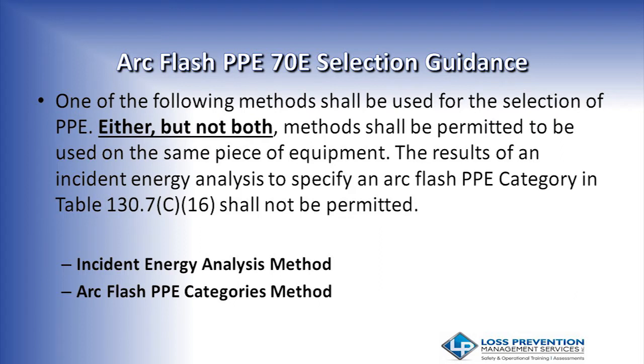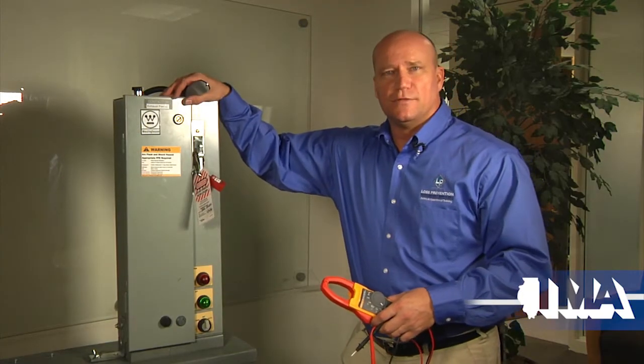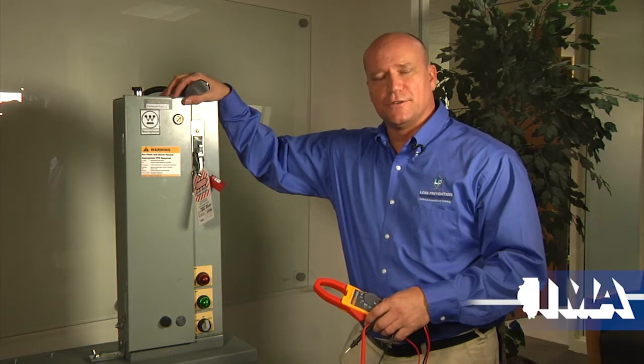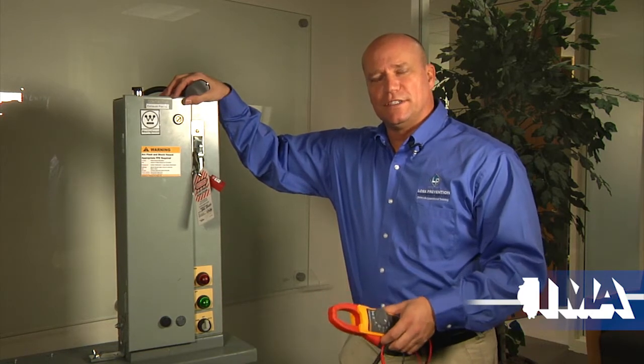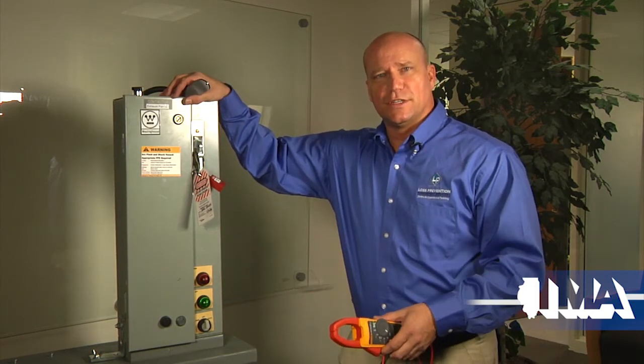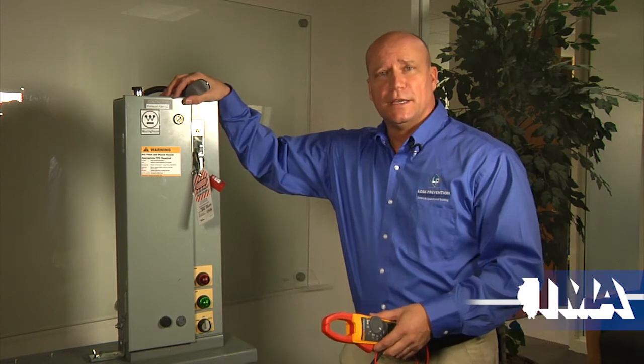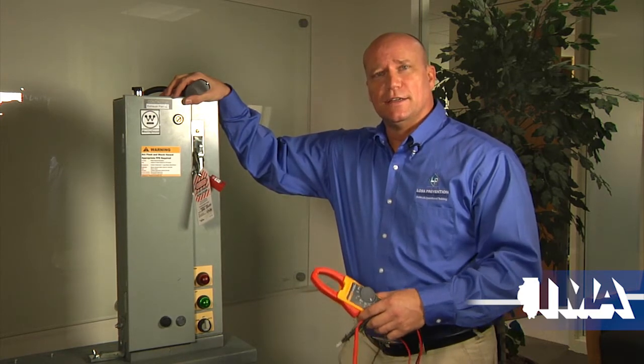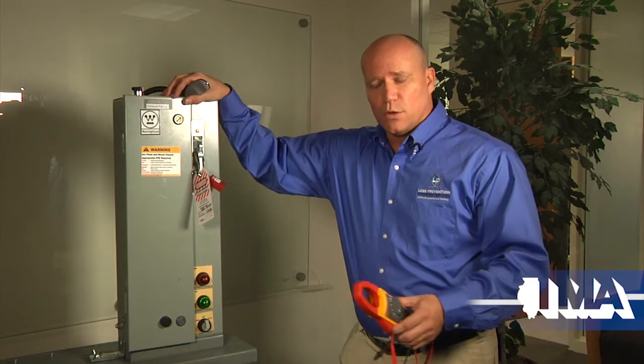Ensure that proper PPE is worn. Personal protective equipment is important. People assume that because I tagged it out, that means there's no voltage. You have to assume it's energized until you've proven it. In that regard, you have to take all precautions as if you're working on energized equipment, because at that point you don't know. Until that last live test is done, you have to make sure you protect yourself. So we're going to talk about that.